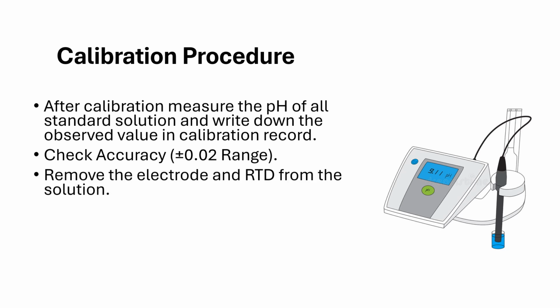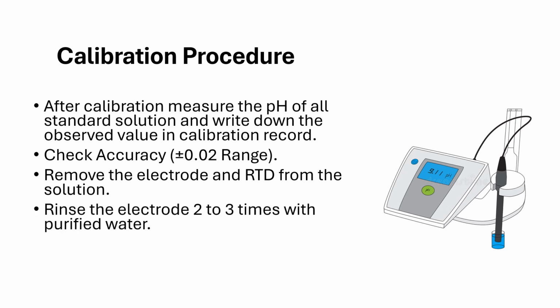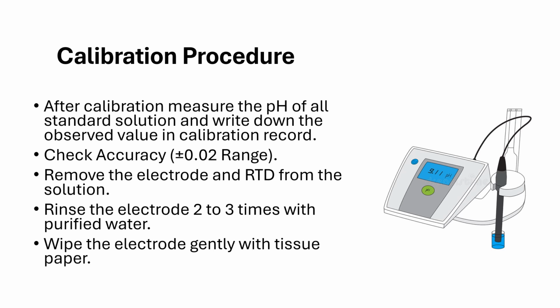After recording the measurement, carefully remove the electrode and the RTD sensor from the solution. Then rinse both the electrode and RTD sensor 2 to 3 times with purified water to wash off any residue. Now gently soak any excess purified water from the electrode and RTD sensor with tissue paper.